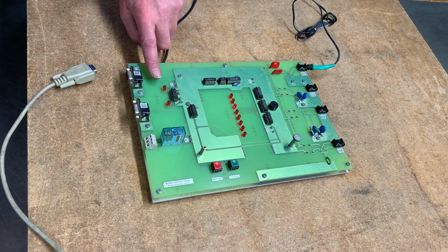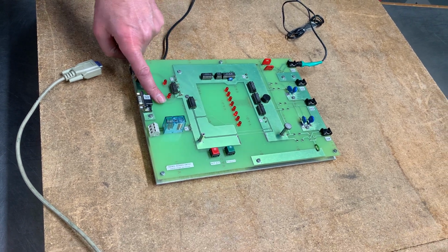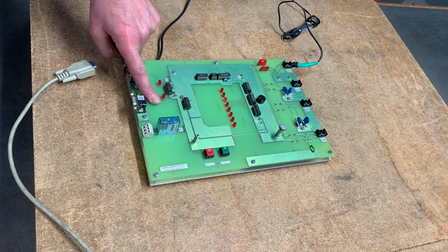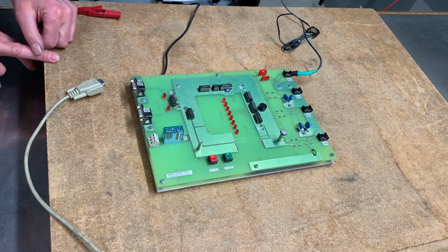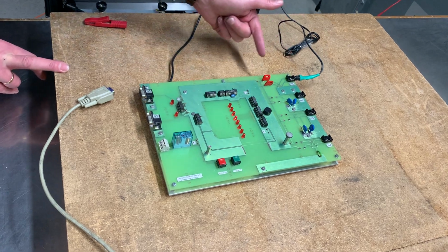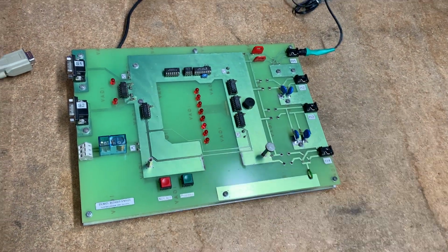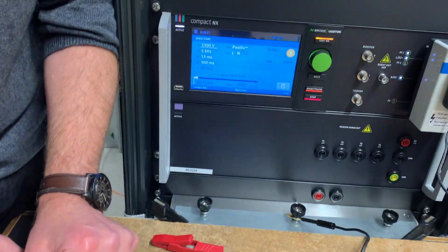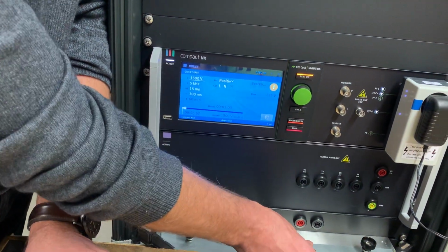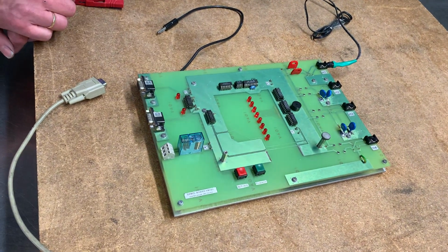For example, simply putting only the finger there, then you see effects. Put the finger on that, you see effects. So, sure, that is EMC, because maybe this suppression is not good enough. Again, I have got 1500 volt. When I disconnect the grounding, in this moment it works.